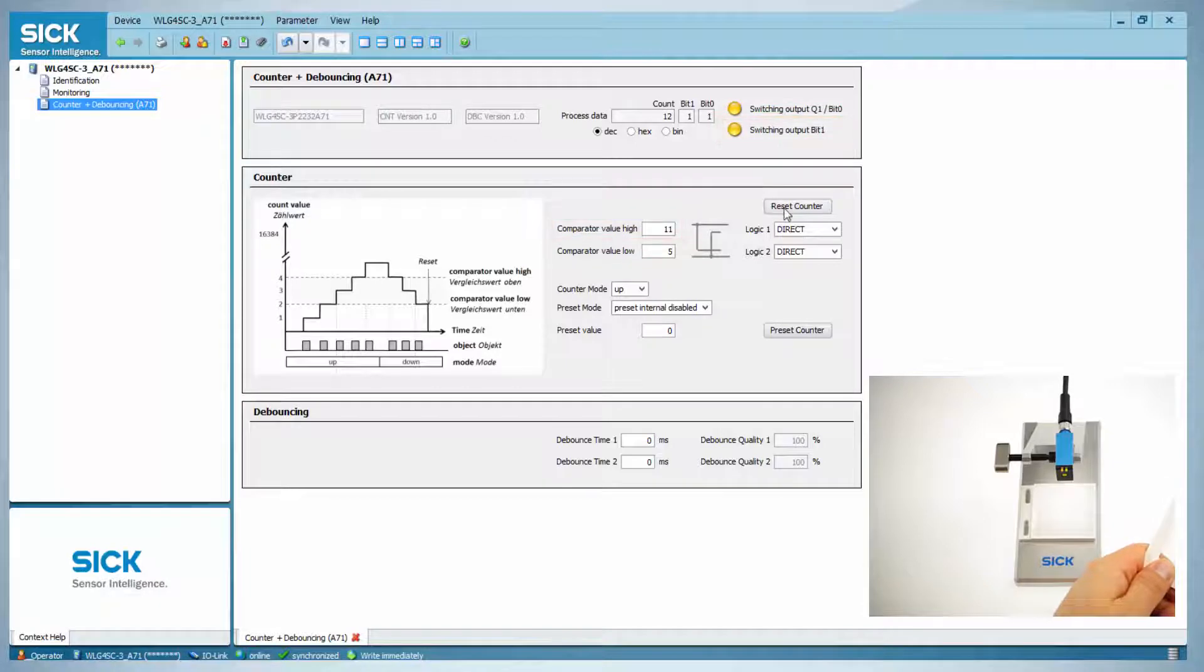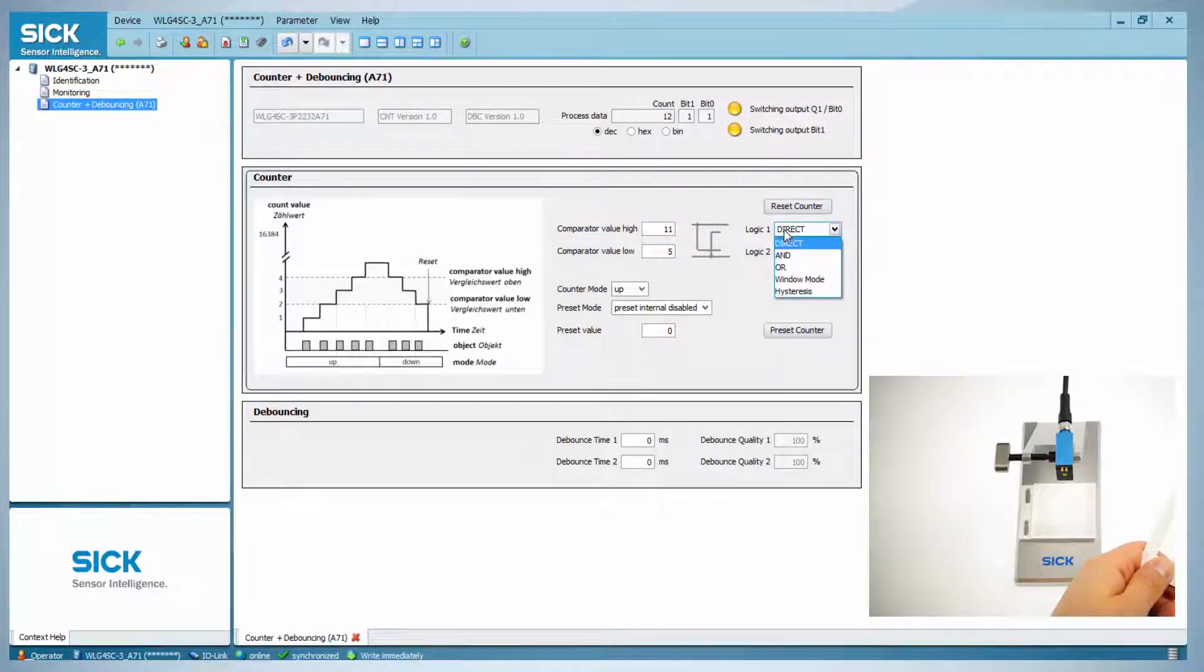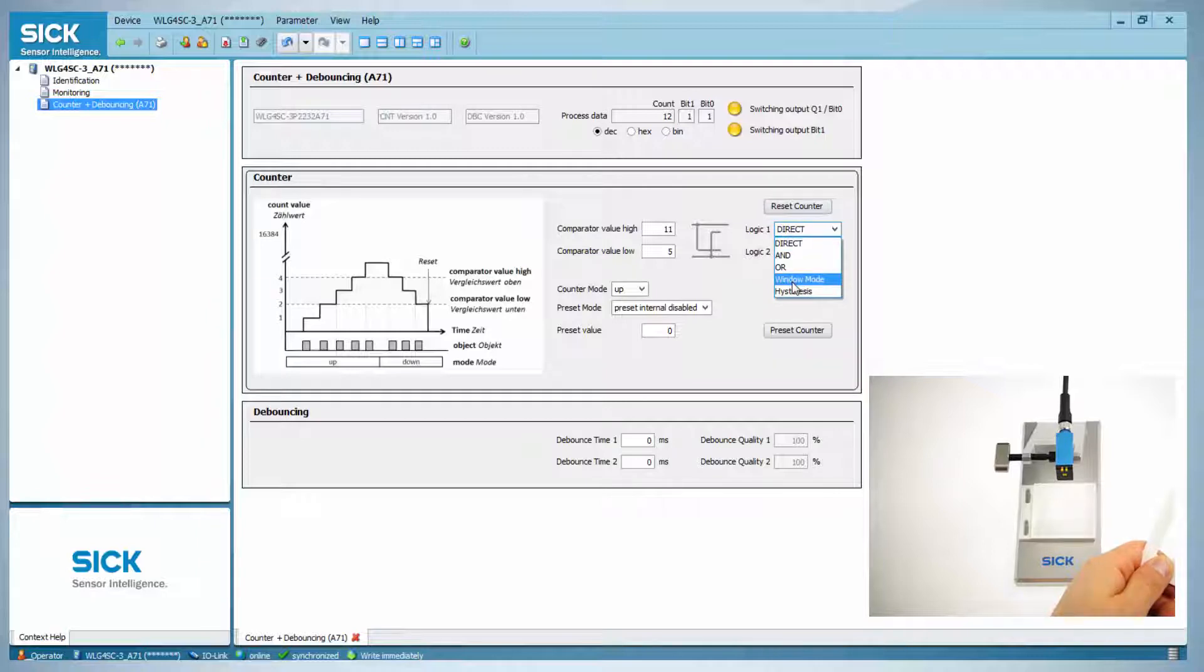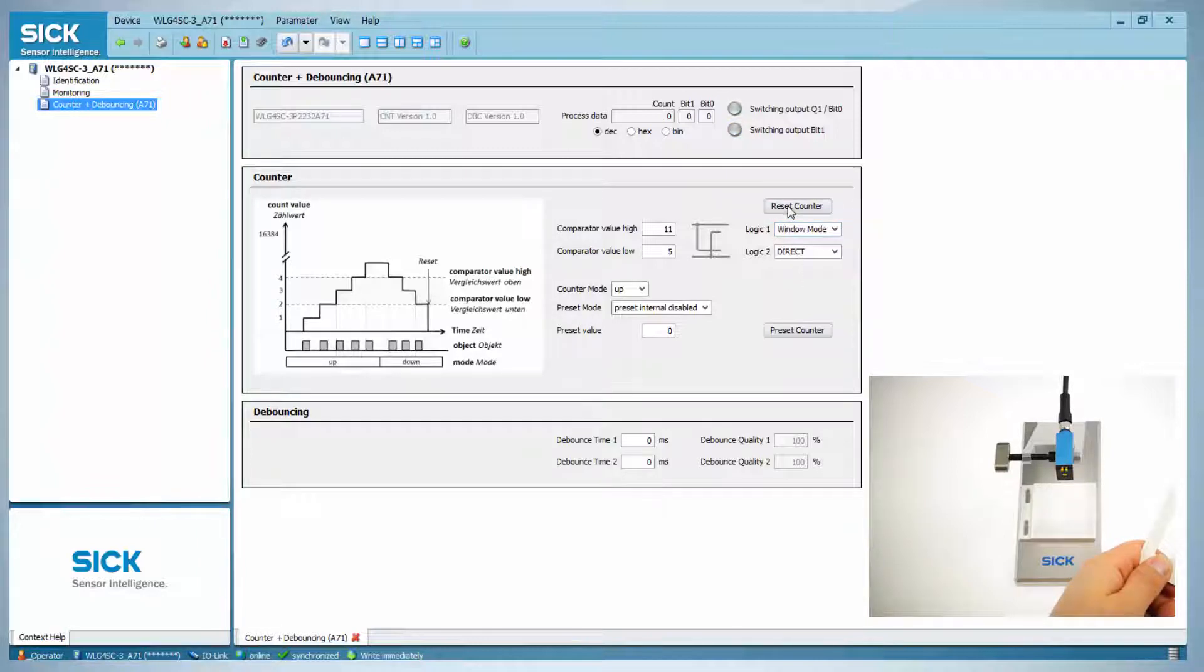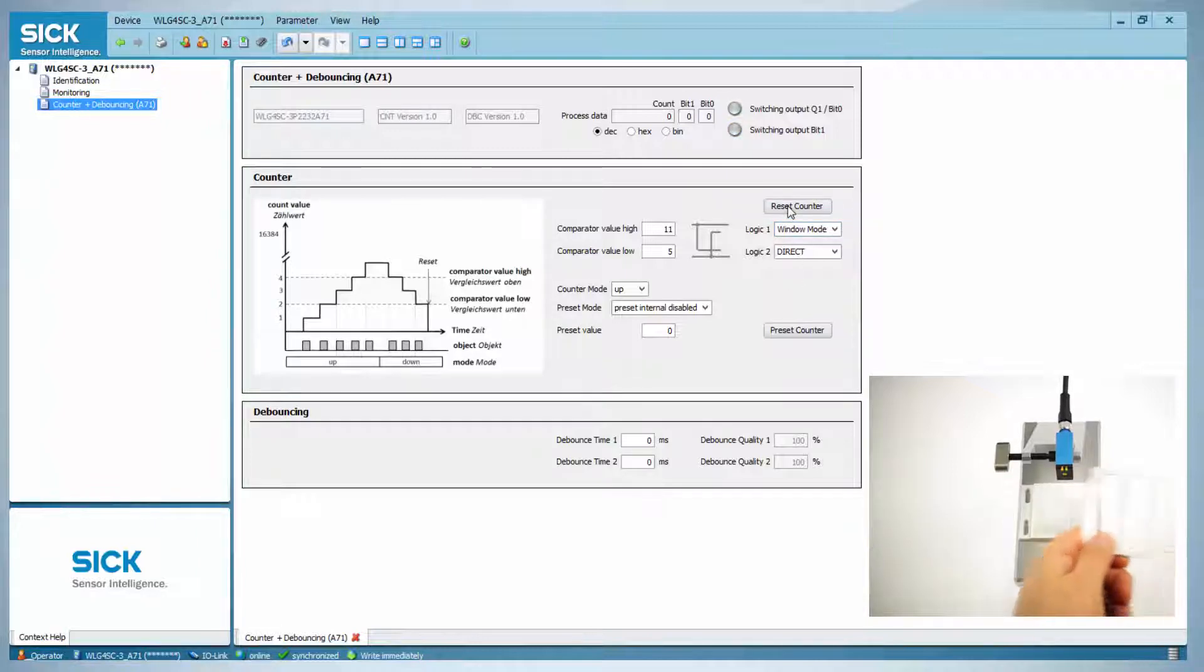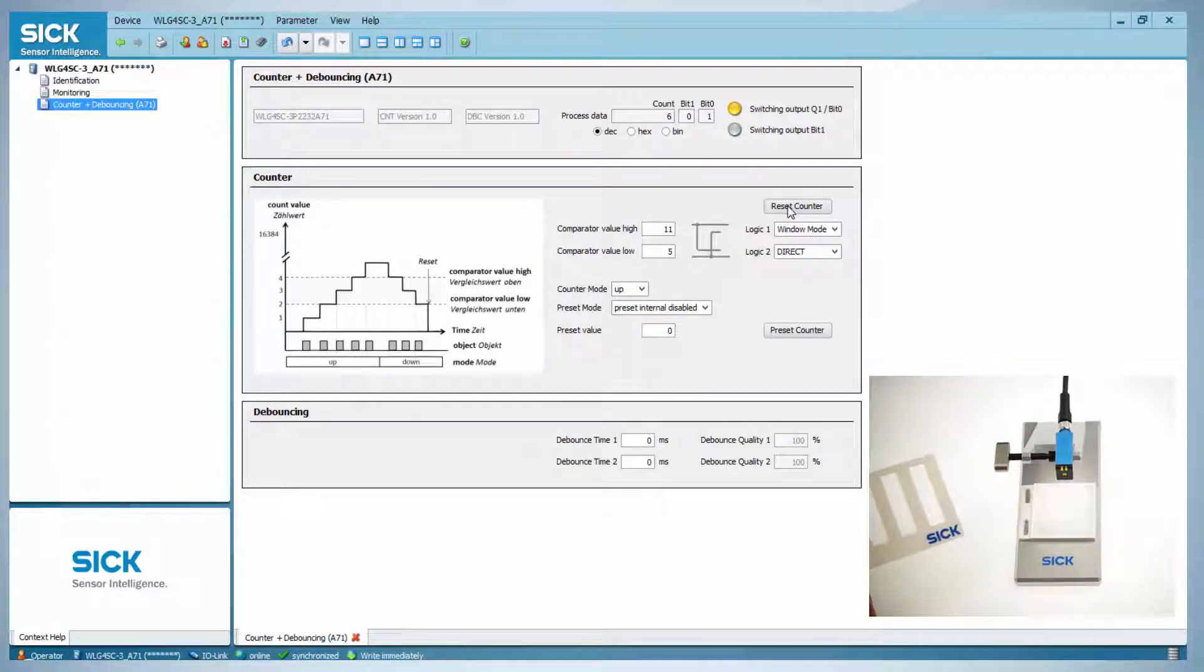The current logic function is direct. If this is changed to window, a windowing function is applied. With the current settings, changing logic 1 to window will result in Q1 being high between 6 and 11, and low below 6 and above 11. Like this, a window is generated.